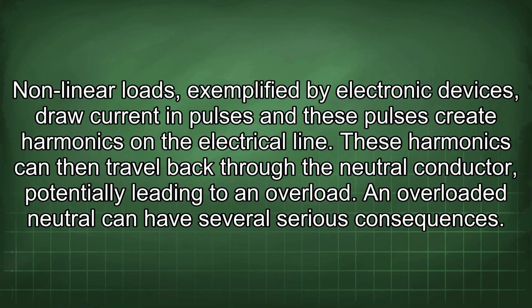Nonlinear loads, exemplified by electronic devices, draw current in pulses, and these pulses create harmonics on the electrical line. These harmonics can then travel back through the neutral conductor, potentially leading to an overload. An overloaded neutral can have several serious consequences.